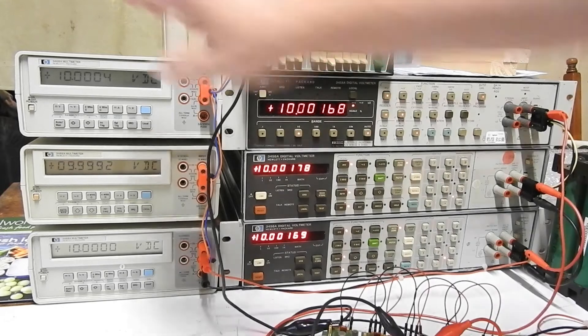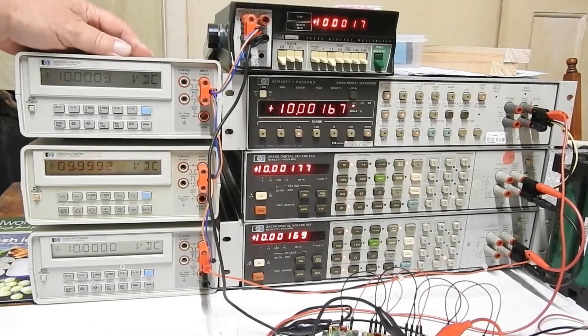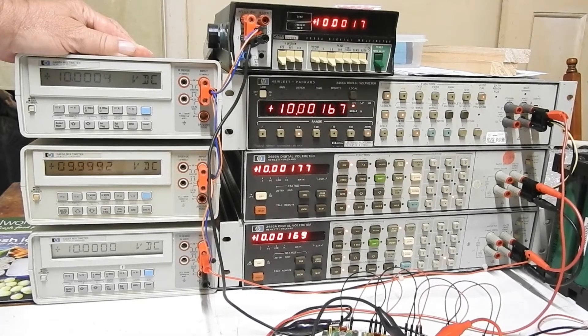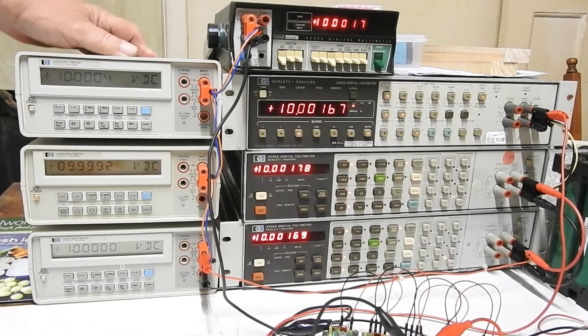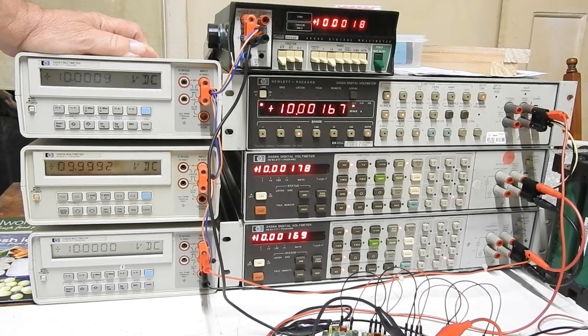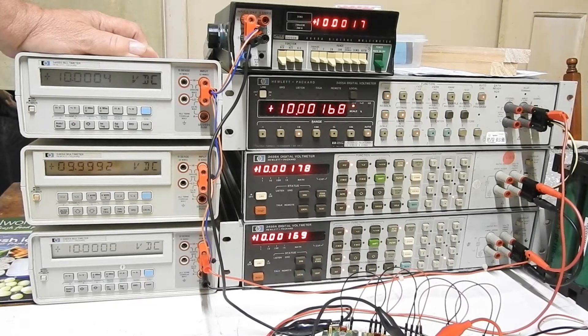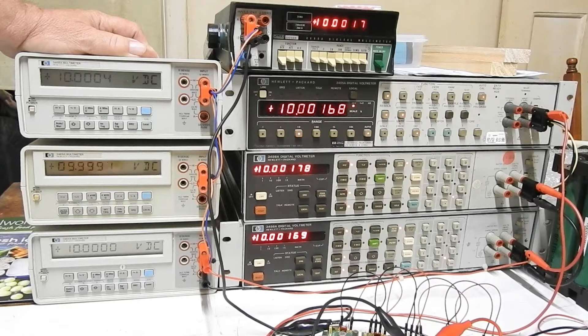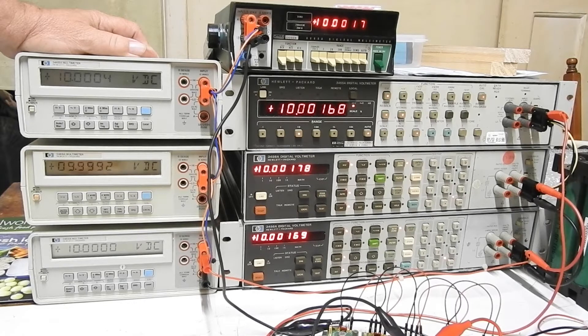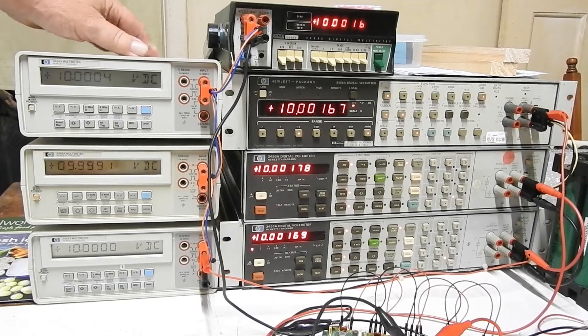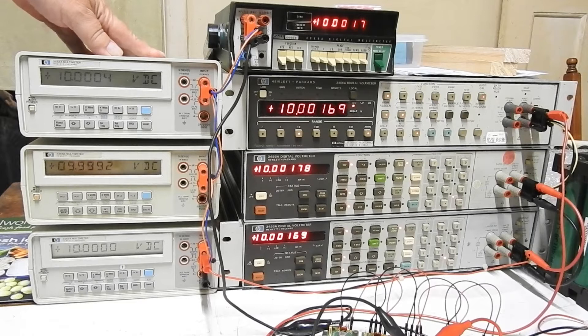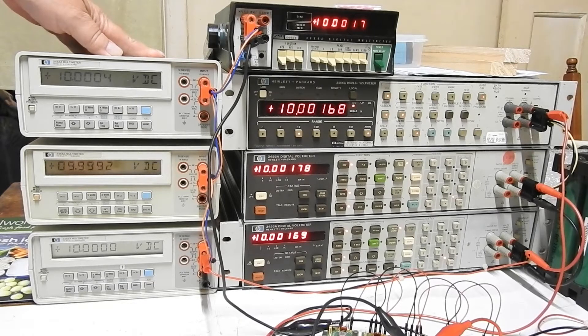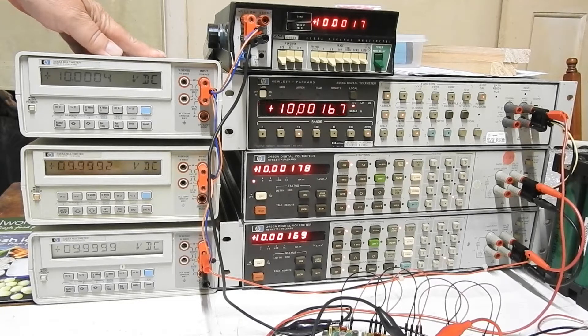These things have a few issues that concern me, not least of which is the rotten LCD display. I would love to do something about that, like minimum backlighting, but preferably replace them with OLEDs. But that's a long-term project. A more immediate concern is that the calibration data inside them is stored in a CMOS RAM chip, which is backed up by a battery. Obviously, if the battery fails, the calibration data disappears.